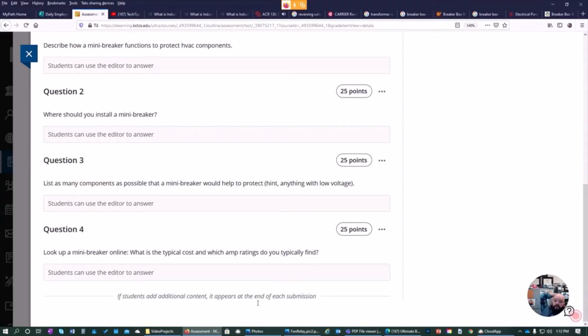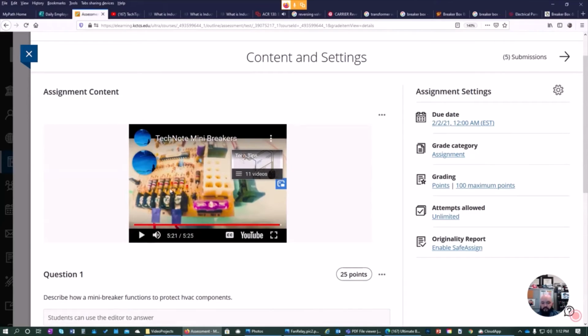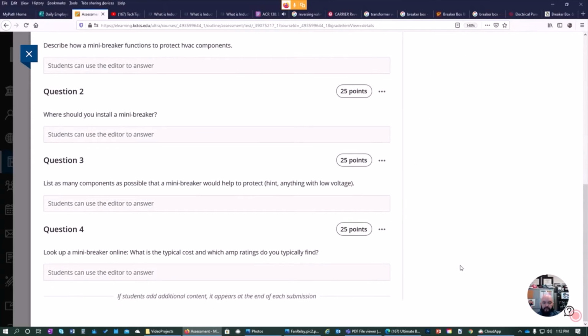You can find mini breakers for amps all the way from 0.5 amps to 50 amps or 60 amps. However, the type we use in our business are 3 or 5 amp mini breakers for circuit boards, and they're typically $6 to $12. So make sure before your test on Wednesday you watch this tech tip video, and if you have any questions, let me know and I'll ask right now. Does anybody have any questions about mini breakers, their purpose?